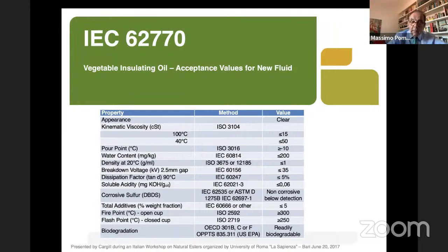And this is also for distribution transformer when we are using inside the building. Of course, a lower quantity. Imagine one transformer of the power rate of 400 kilovolt amps. It means that you are using something like 400 liter of insulating liquid, and it is insulating liquid is the products coming from crude, from petroleum. Imagine that when we have a fire, what happened, and I will show you some picture later on.